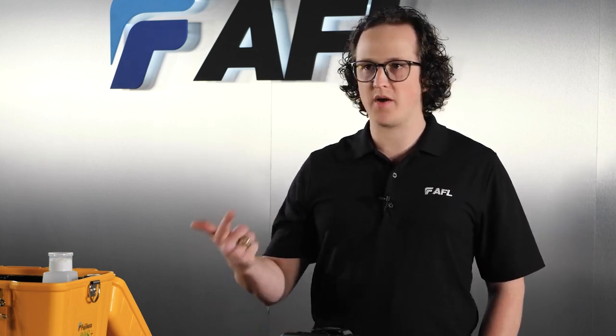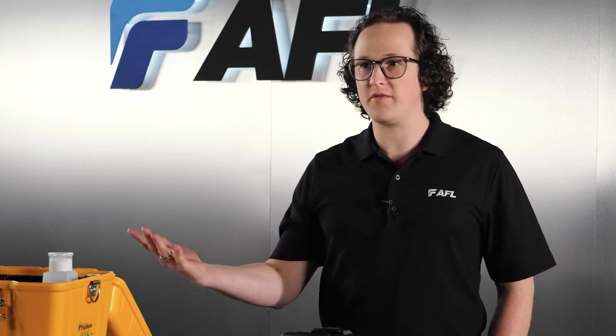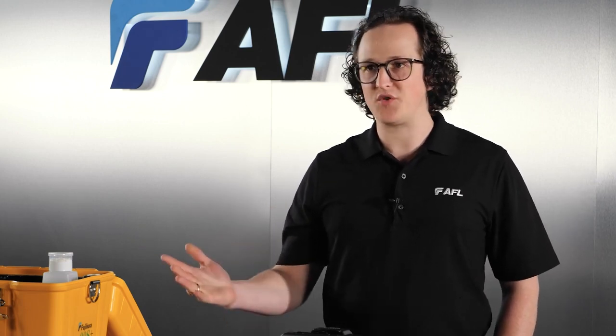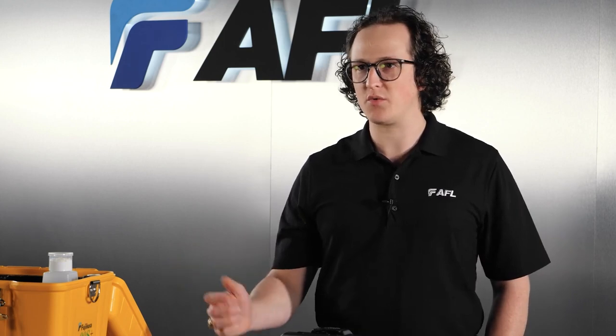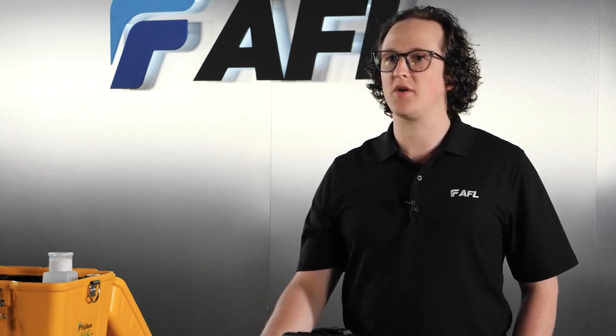Conditions like temperature, barometric pressure, and humidity all affect how much arc power you need in order to precisely melt the fibers. And since every day has different conditions, start the day with a quick arc calibration to get you started, then use a splice mode ending in Auto to keep the initial calibration accurate as the conditions of the day evolve.